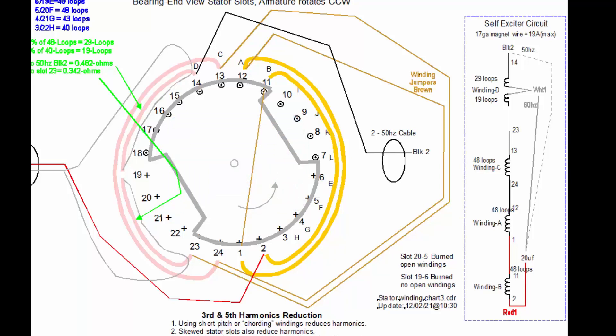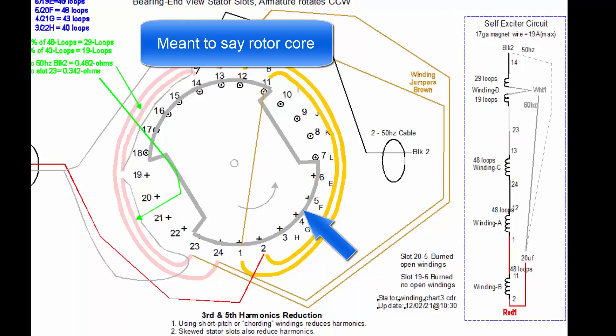This allows the 50 Hz to have nearly the same voltage when it's running the engine slower. And the capacitor, you can see it down here, it says 20 microfarad capacitor. It runs between either the 60 Hz connection, which is white up there, or it runs to the black two, which is a 50 Hz connection. And either way, it charges and saturates the stator core with its magnetic flux.